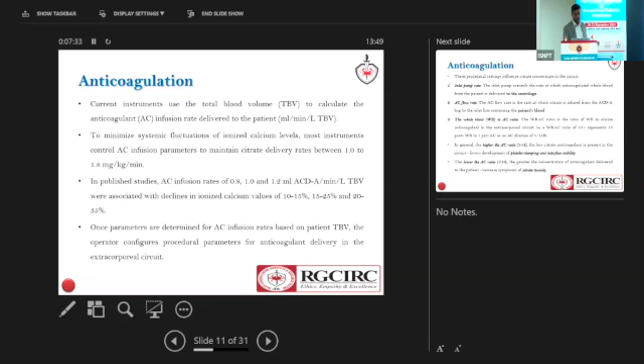Once the parameter of ACD infusion rate is fixed, the operator can configure the next procedural parameters. Once we finish with the patient, we can go for the extracorporeal circuit. In the extracorporeal circuit, or in the machine itself, there are three main points which have to be considered. First is the inlet pump rate, which delivers the anticoagulated blood to the centrifuge. The second is the AC flow rate, which delivers the ACD to the patient's blood, and finally the whole blood to AC ratio.